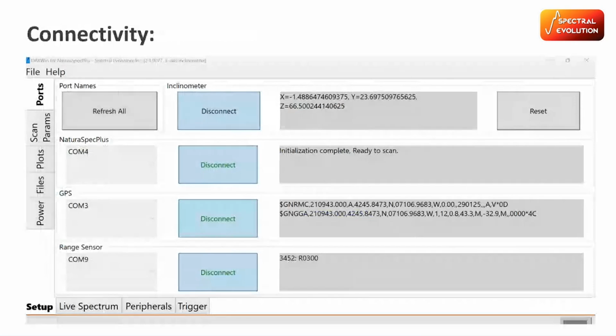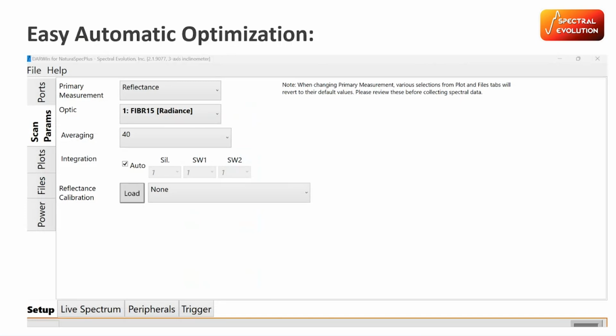It also has easy connectivity with all of our different new sensors on it, as well as the instrument. They're simple. It's just one button to connect to each, and you can reset them with one button as well. So getting started in the field is a quick and easy operation to optimize how much sampling time you're going to have. We also have the same kind of optimizations and customizations that you can do with all of our other instruments. We have the optic selections, so you can have radiometrically calibrated lenses and diffusers, and you can select what kind of averaging you're going to do for your field procedures. There's also the auto integration, which is that optimization step that is optional, but I recommend keeping it on for most applications. And then reflectance calibrations can be loaded in here as well.